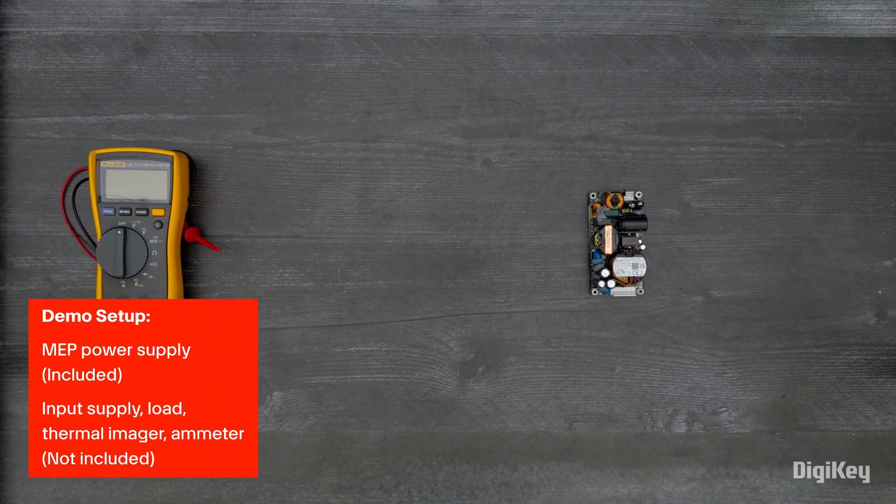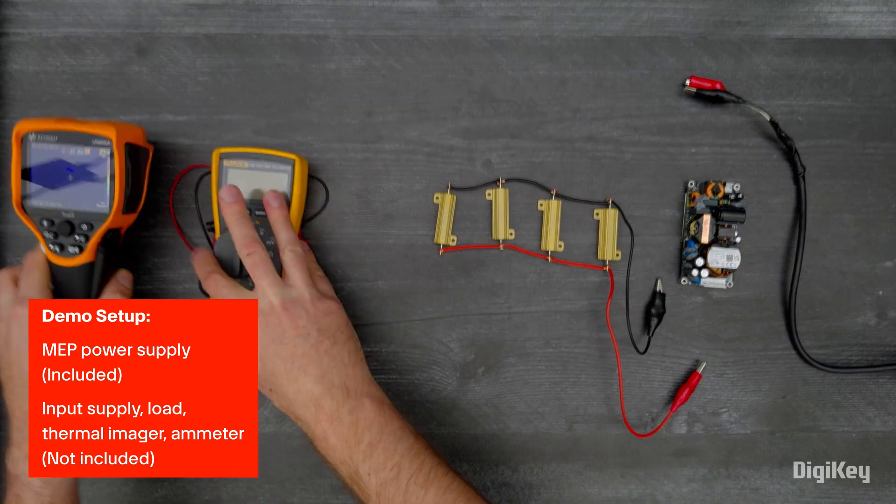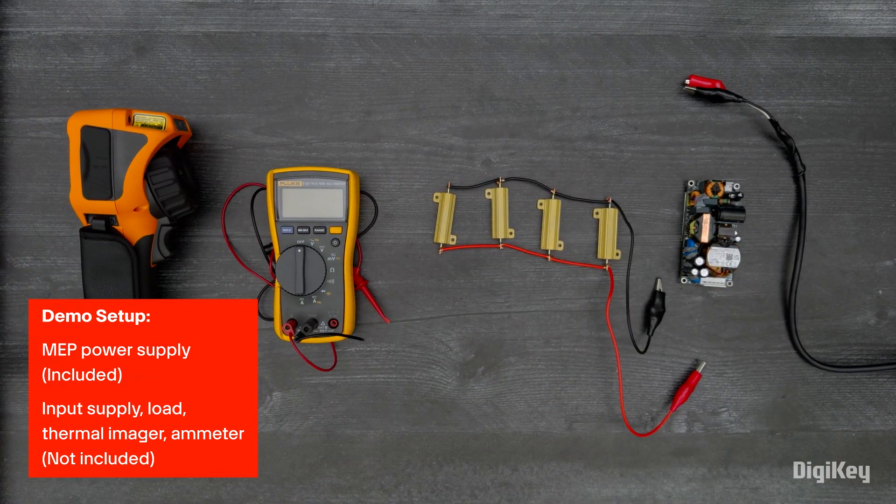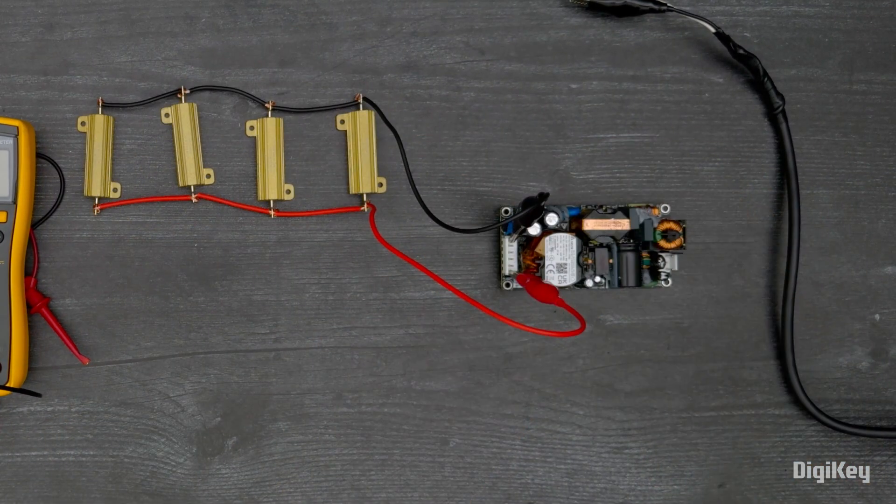Here we'll demonstrate the MEP series open frame power supply's high efficiency performance at 96% load with thermal imaging. First, we're going to connect our load to pins one and four on the output connector.